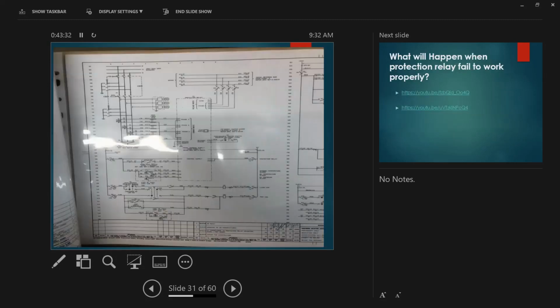I just want to add something on that drawing as well, because most of the time, young engineers just do connection testing without analyzing the drawing and the scheme. Sometimes we always forget the breaker failure. Yeah. Especially when we're doing it in-service. The breaker failure is very risky when we're doing relay testing because the relay will also send a signal upstream, which sometimes causes a big issue. It will drop the whole supply in that particular area.